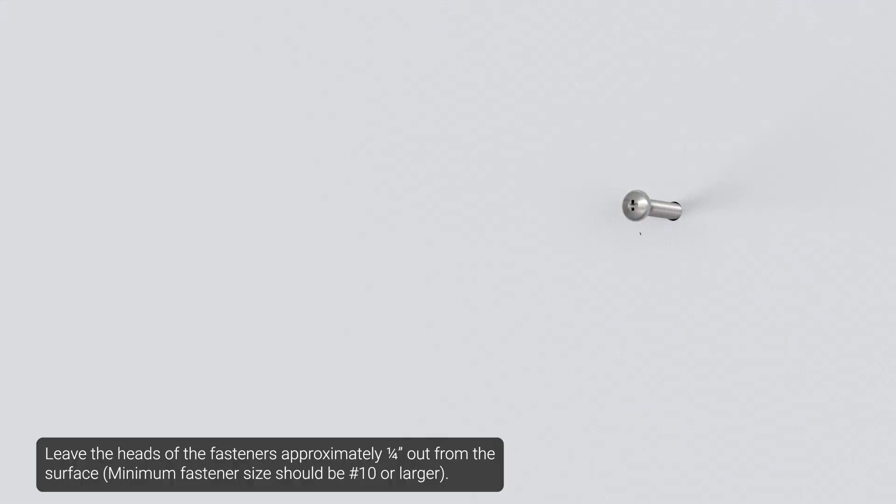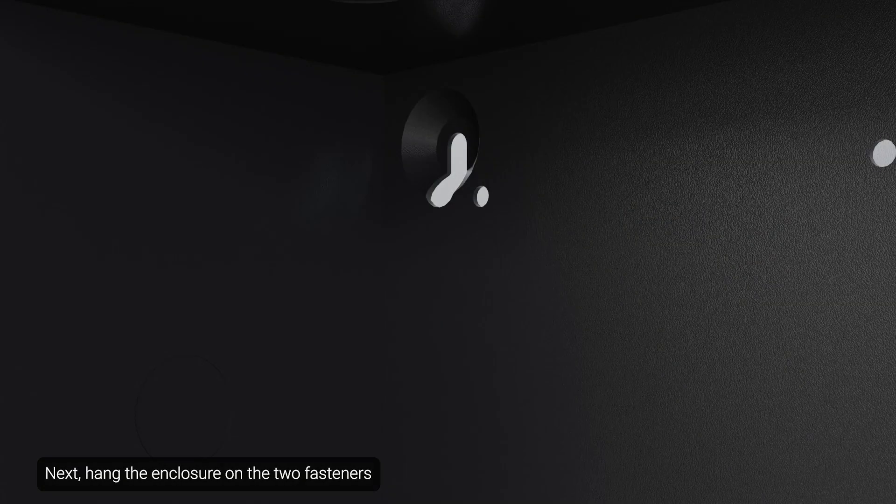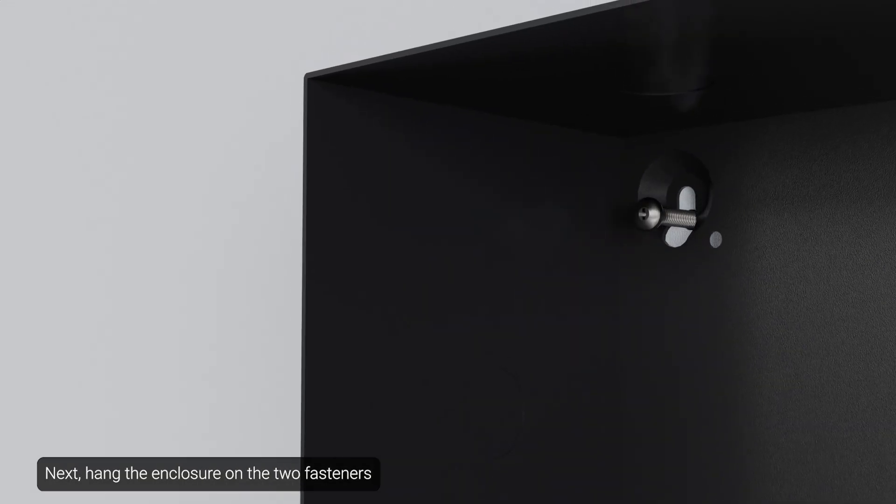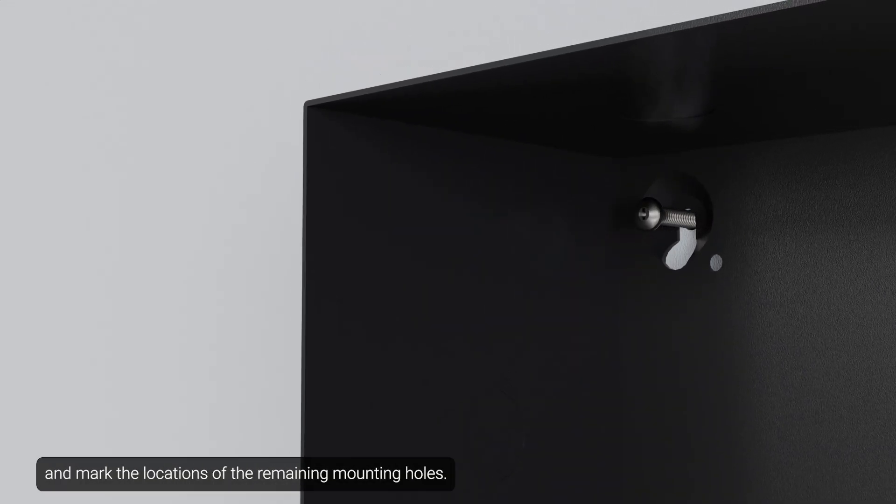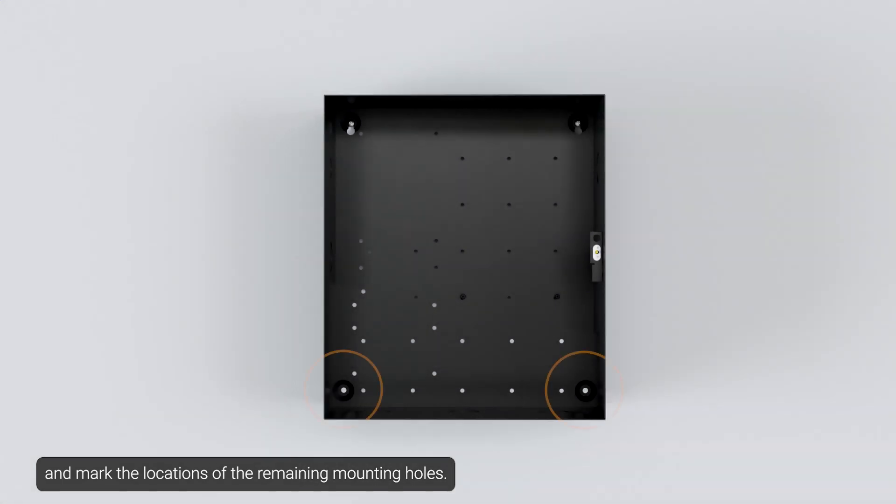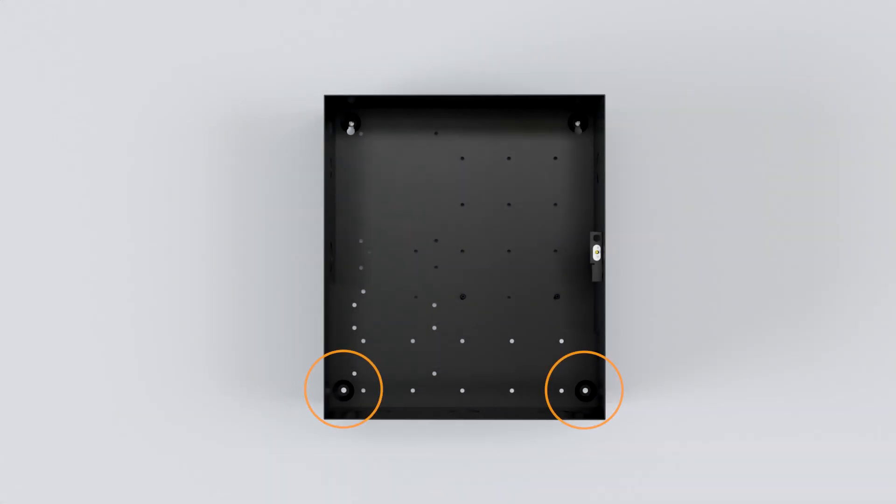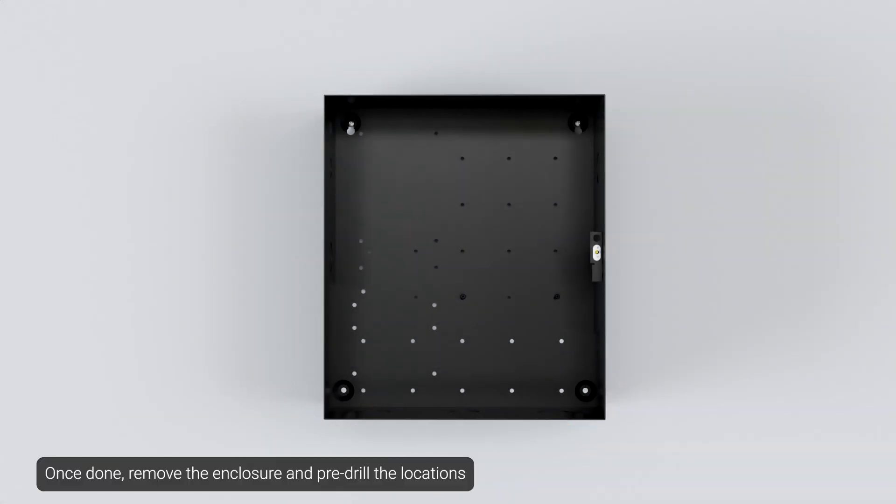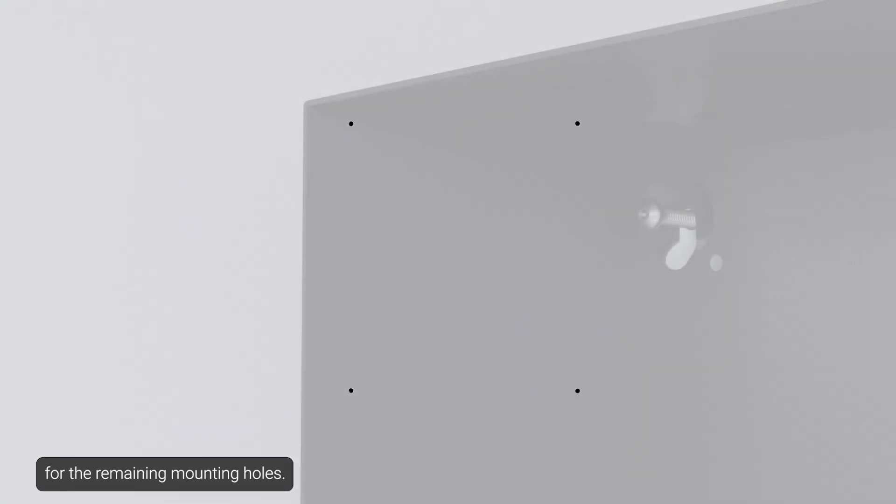Partially install two fasteners to the surface on which the enclosure is being installed. Leave the heads of the fasteners approximately one-quarter inch out from the surface. Next, hang the enclosure on the two fasteners and mark the locations of the remaining mounting holes. Once done, remove the enclosure and pre-drill the locations for the remaining mounting holes.